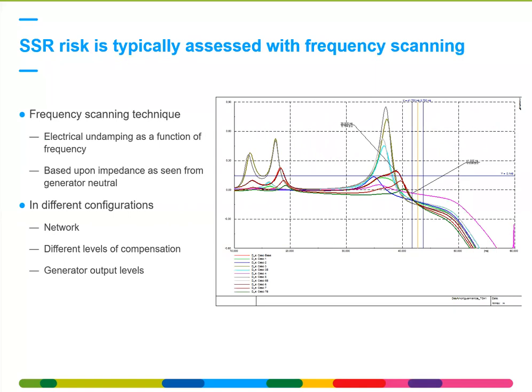Typically, the risk of having such an interaction with the grid for the SSR is assessed by frequency scanning. So how is this done? Well, one looks from the generator towards the grid, and then the electrical undamping or the impedance is determined as a function of frequency. So for every frequency in the grid, you have the impedance or the electrical undamping, and this has to be related with the mechanical side.